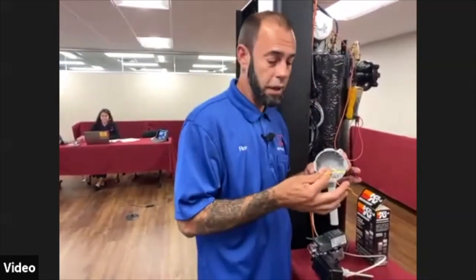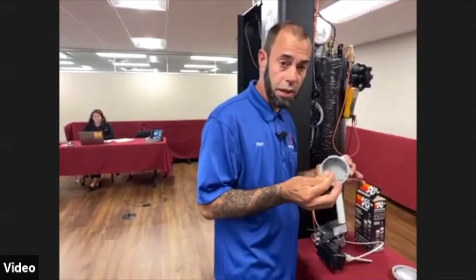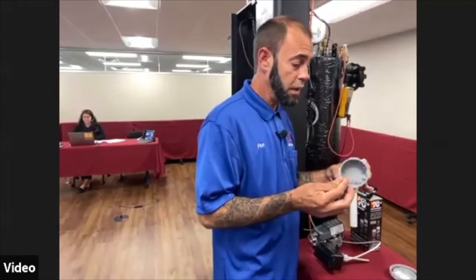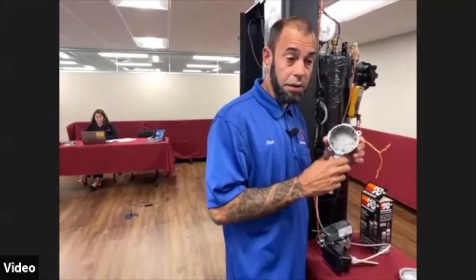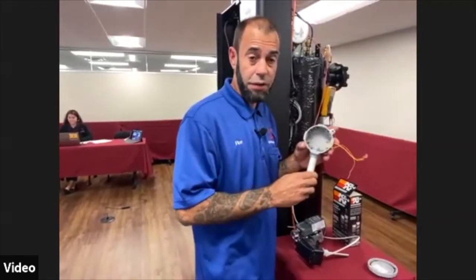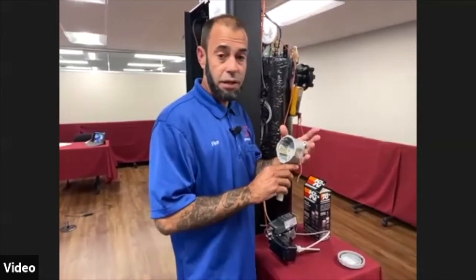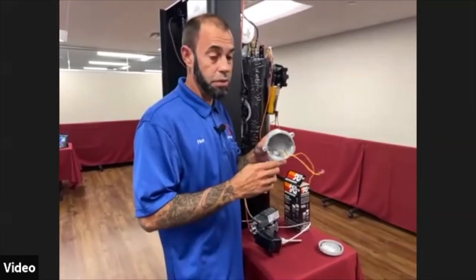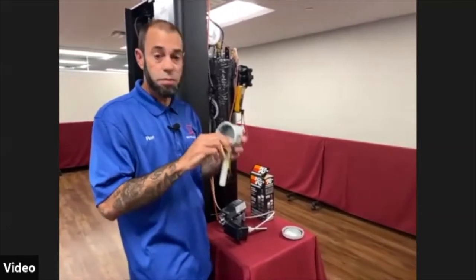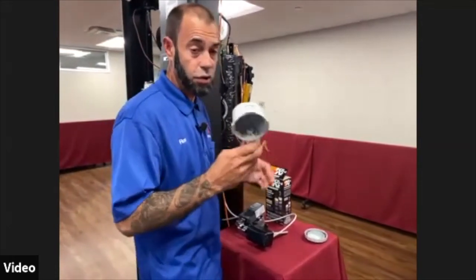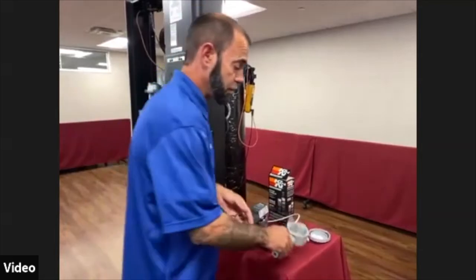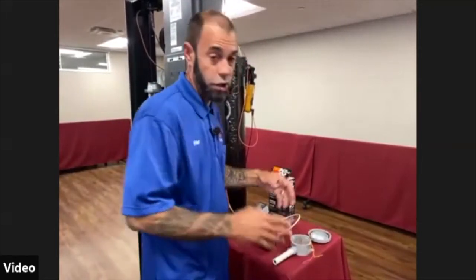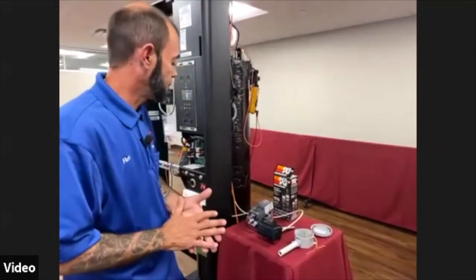Outdoor sensor. Outdoor sensor is also a 1 k ohm at 70 degrees. Recommend mounting this outside, out of direct sunlight, off of anything that might be hot and be able to potentially transmit additional heat to this, causing you to get incorrect outdoor temperature sensor readings, which will change your outdoor reset schedule, of course.